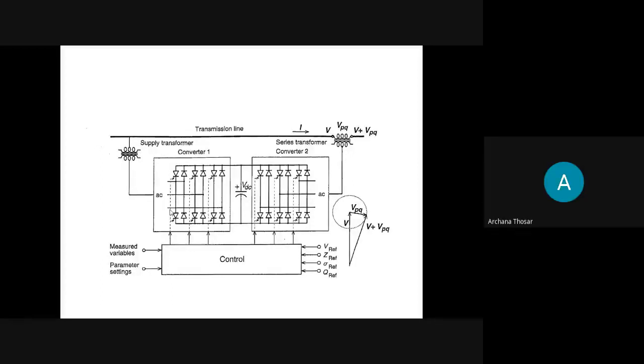The real power can freely flow in either direction between the AC terminals. They are connected to the AC side, so the real power can easily flow from this side through these two converters, and each converter independently can generate or absorb reactive power at its own output terminal. Are you understanding the beauty of this?